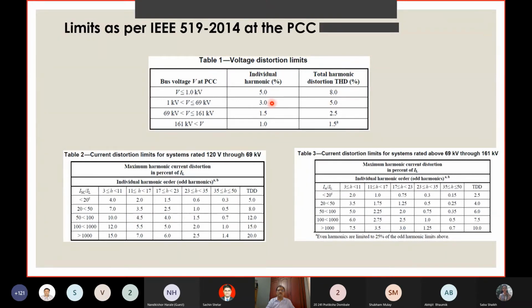That is 3rd order, 5th order, 7th order. The limit is 3%. So whenever we go and make a study, we'll have to understand whether it is below 5% and also individual order harmonic is below 3%. And then comes the total demand distortion, which is THD, but instead of fundamental current, it is the load current. The denominator is the load current, and this is based on the ratio of short circuit current to load current.